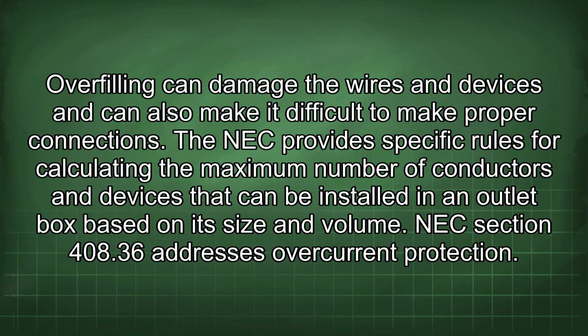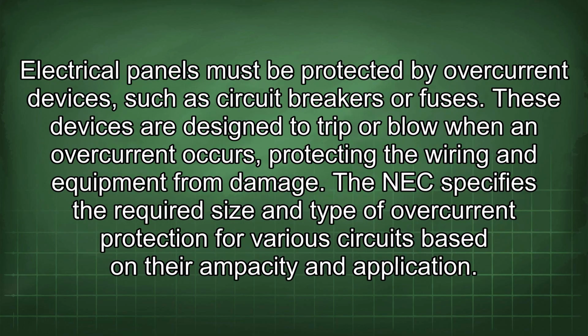NEC Section 408.36 addresses overcurrent protection. Electrical panels must be protected by overcurrent devices, such as circuit breakers or fuses. These devices are designed to trip or blow when an overcurrent occurs, protecting the wiring and equipment from damage. The NEC specifies the required size and type of overcurrent protection for various circuits based on their ampacity and application.